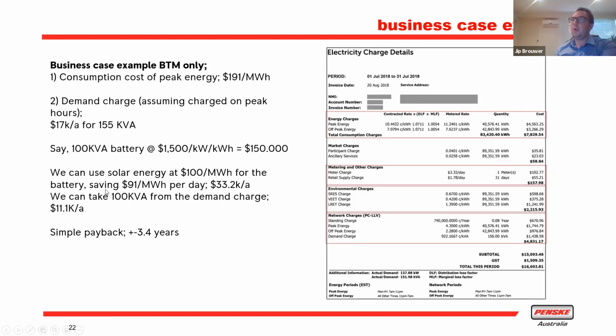If we assume that we can take off 100% of the battery of this 155, you would only have a demand charge instead of 155 kVA, it would reduce to 56 kVA. Then you have a saving of an additional $11,000 per year. Simply adding these two would make it $44,000 a year, and if you divide the capital cost through that annual saving, you get a simple payback of 3.4 years, which for most businesses is quite attractive.